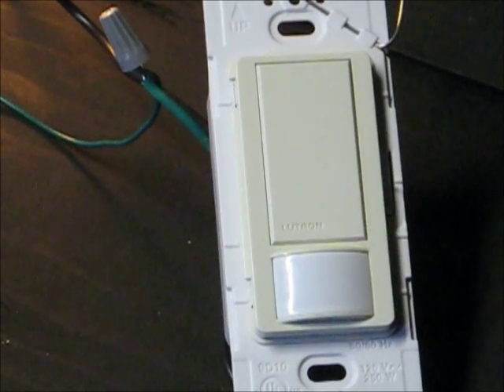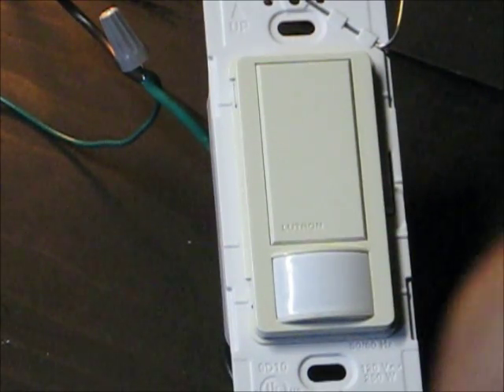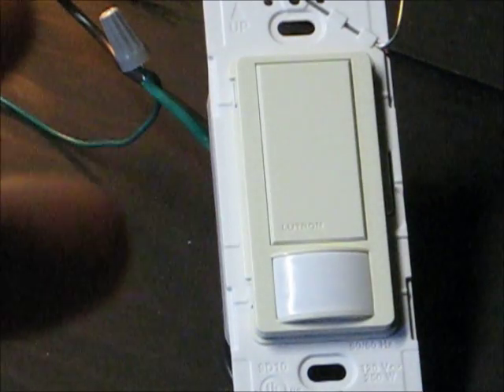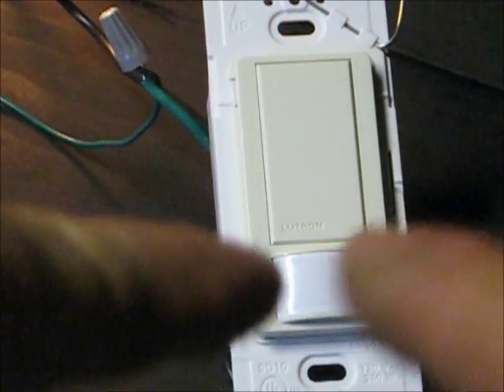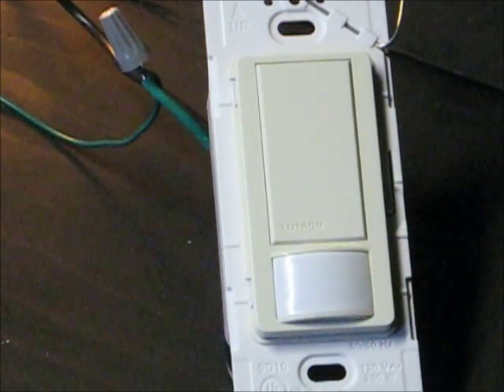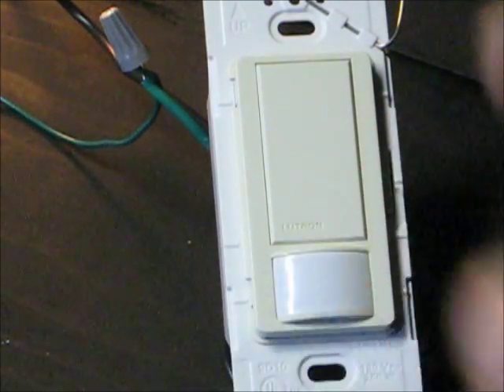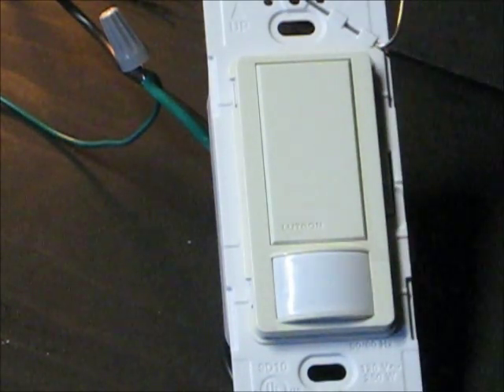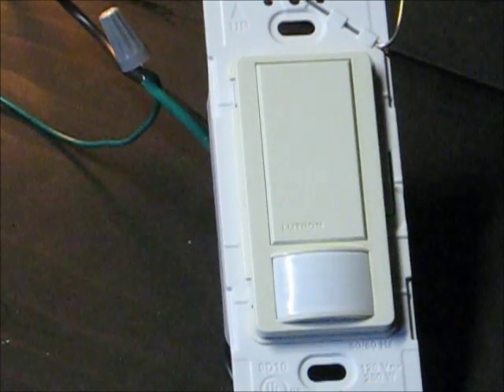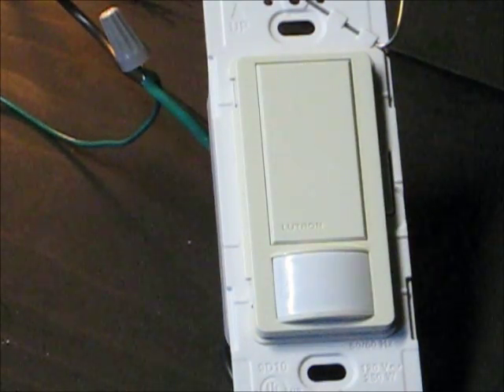Now, you people who've taken my acceptance test technician classes are going, what about the winky light in normal operation? The winky light's not there during normal operation, just in test mode. But California's Title 20 says it's legal for sale, for use in California if it has a status indicator that indicates the device is working properly, and it may be overridden if desired.